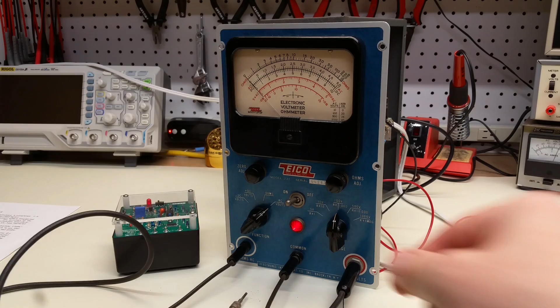This is supposed to be plus or minus 5% accuracy on the AC scale. And so it's very good on the 1000 volt scale and very good on the 500 volt scale. On the 100 volt scale, it read, what, 96? And so 5% of 100 would mean that any reading between 95 volts and 105 volts would be within the range of accuracy quoted on the meter. And in fact, we got that. We got 96 volts. So, you know, we could peak it up to make it more accurate on any given scale, but there's no reason to do that because this is not a high accuracy instrument.